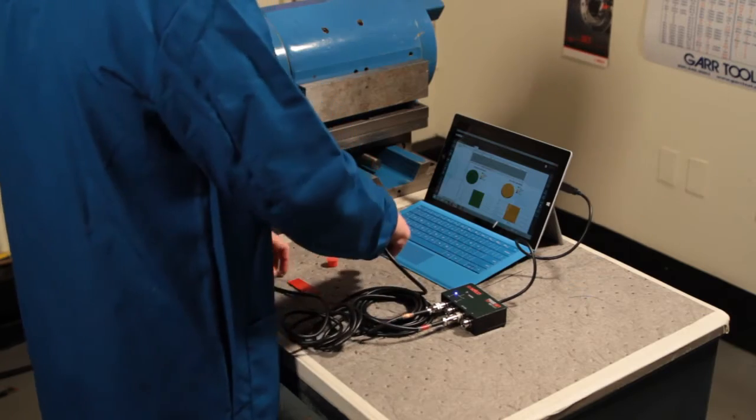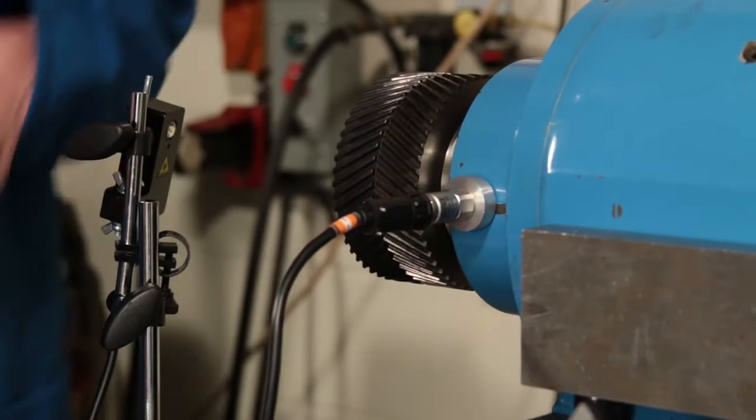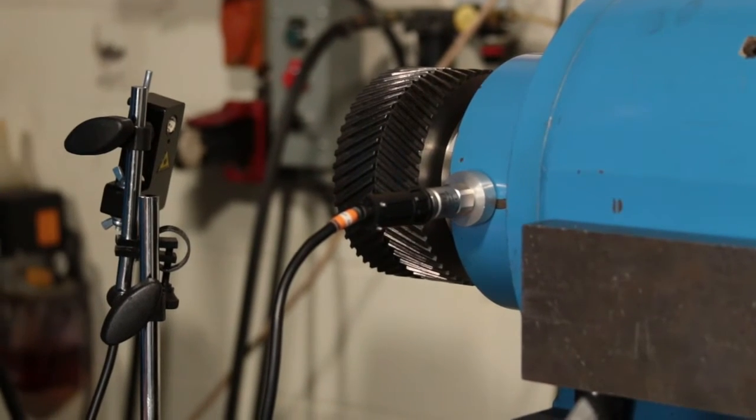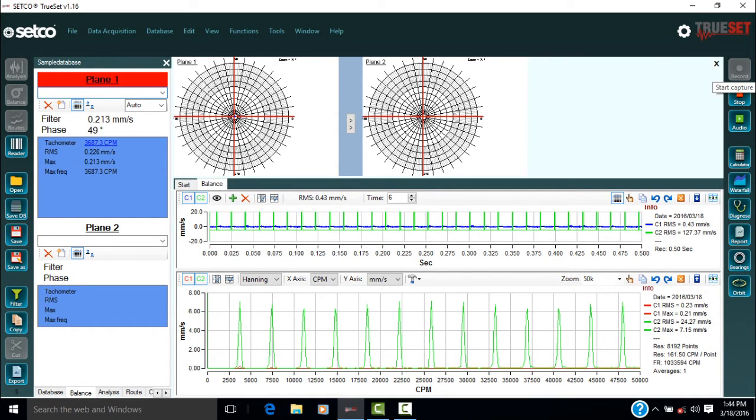Place the accelerometer in the horizontal position. The accelerometer should be as close to the weight plane as possible. With your equipment running, click record to take the initial data. It is a good idea to record two sets of data to ensure the results are similar.